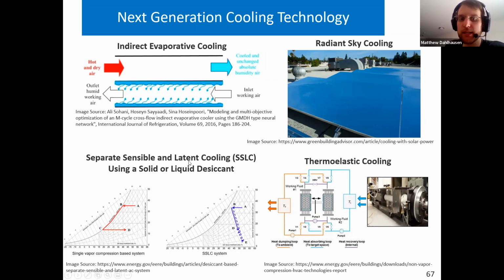Separate sensible and latent cooling systems are a broad class of systems that cool air sensibly with one method, and then use a desiccant to remove moisture from the air. Lastly, there are non-vapor compression cooling technologies like thermoelastic cooling that uses the properties of some materials that gain or release heat when expanded or compressed. These can be a direct replacement for vapor compression systems, but have not yet been commercialized.